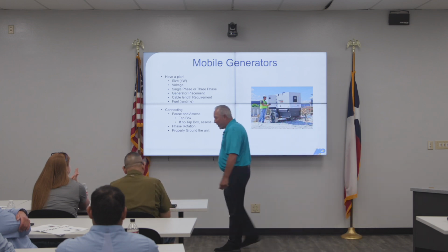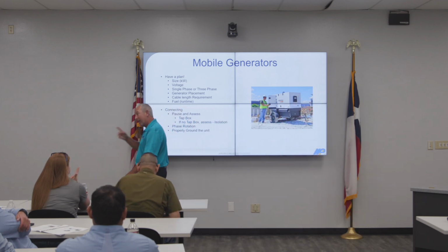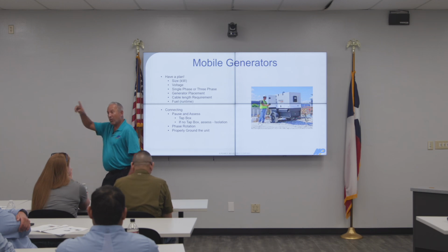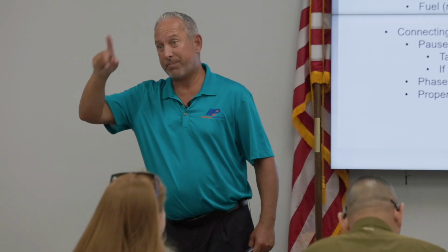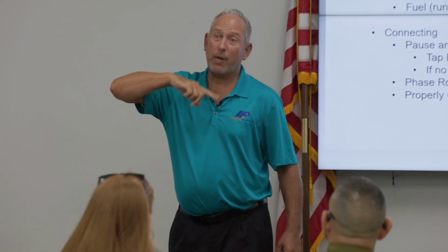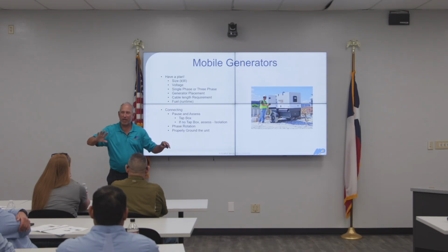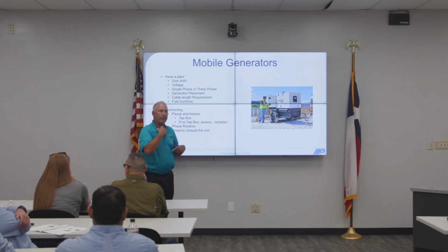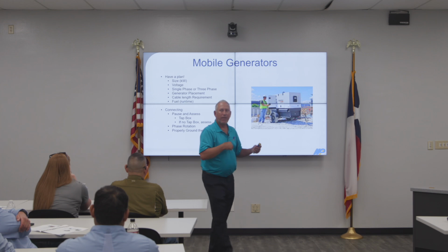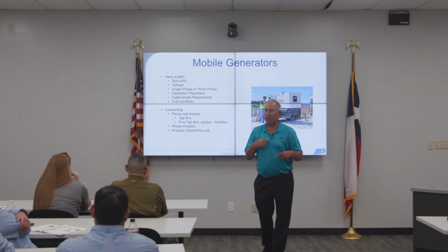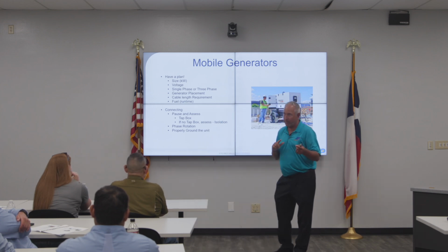The other thing you need to know for a three-phase building is phase rotation. Are your loads going clockwise or counterclockwise? Not a big deal - if it's wrong, your motors are just spinning the wrong way. Generally no harm, no foul, but you have to stop and switch two leads around so it goes the right direction. So knowing your building's phase rotation ahead of time is good, otherwise you'll have to redo what you just did.